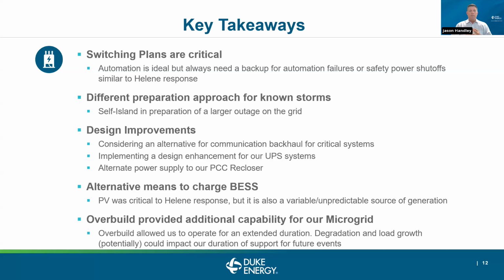Also, from a UPS system standpoint—that stands for uninterruptible power supply—basically, when I talk about batteries, I always say my big batteries take small batteries to work. So when the power's out, small batteries are used to ensure the communications, automation, and all the logic controls work. Well, after 3 days, all my small batteries were dead by the time we got to the site, so we had to charge those back up. We've now made an enhancement to the site: an on-site 50 kW generator to take care of these backup power supplies, to keep our bigger batteries online for a longer amount of time. So, alternative means to charge the battery energy storage system, or BESS, which stands for battery energy storage system.